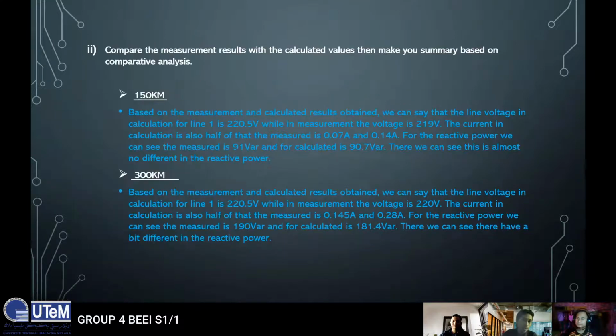For the next question, question 2: compare the measurement result with the calculated value, then make your summary based on comparative analysis. For the result for 150 km, based on the measurement and calculation results we obtained, the line voltage in calculation for line 1 is 220.5 volt, while in measurement the voltage is 219 volt. The current in measurement is half of the calculated one: 0.07 ampere measured, and 0.14 ampere calculated. For the reactive power, the measured is 91 var, and calculated is 90.7 Var. There we can see this is almost no difference in the reactive power.